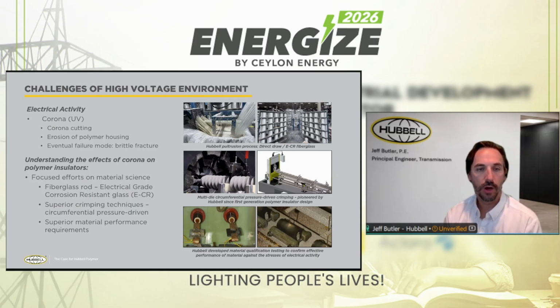What that meant is it led to the focus of the performance of the insulator in those areas. So for Hubbell, we had good performance with our insulators previously because of the design, and I'll talk about that a little bit later when I talk about our insulator design. But it did mean that there was an increased understanding in the industry of the effects of the electrical activity and corona for these polymer insulators. So that meant that there was an evolution in fiberglass rod, for example, where electrical grade was acceptable, but then everybody evolved into electrical grade corrosion resistant glass. It also led to the broader acceptance of a crimping technique referred to as circumferential crimping. And this was a crimping technology that Hubbell helped pioneer back in the 70s, but the industry came to widely accept that in the 90s. And today, almost every polymer insulator manufacturer is using circumferential crimping. And then it led to further advancement of materials, of polymer, of rod, of bonding, of molding of insulators.